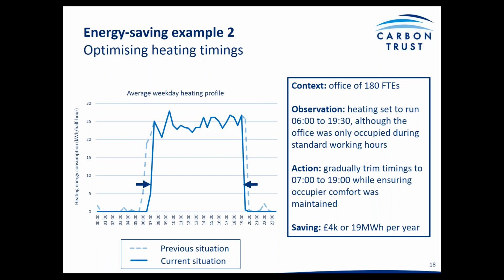Another example of analysing data can be found in the data set shown on your screen. An office of approximately 180 employees, slightly lower than the previous example, with access to half-hourly data. During the heating season, it was quickly identified that the heating system was being controlled by both time schedules and weather optimization controls, so there was potential for improvement.